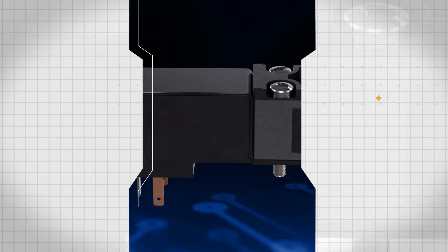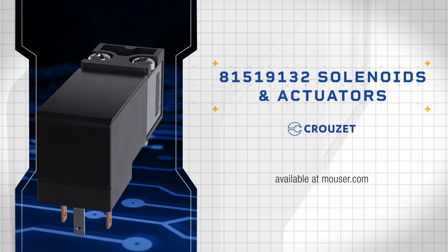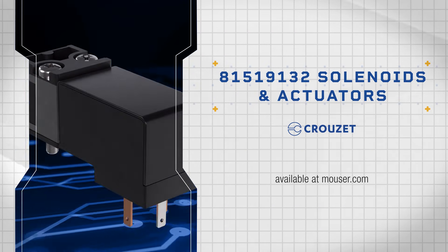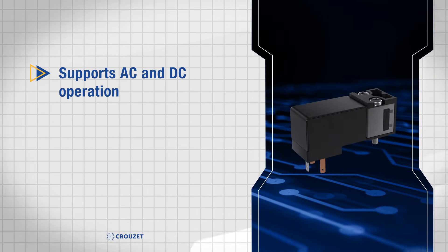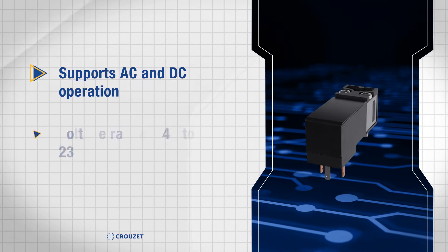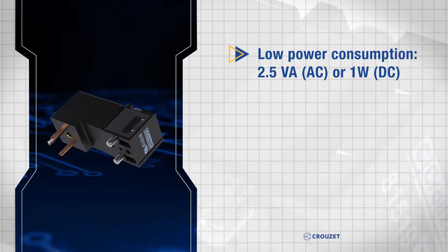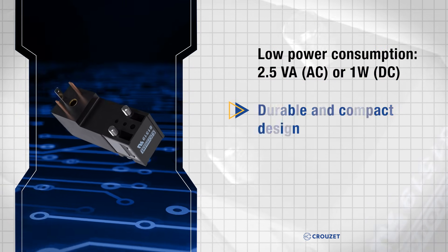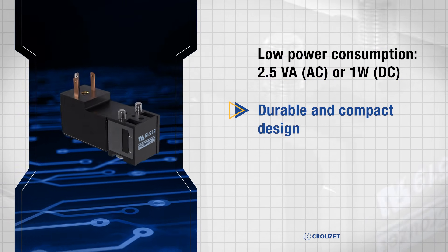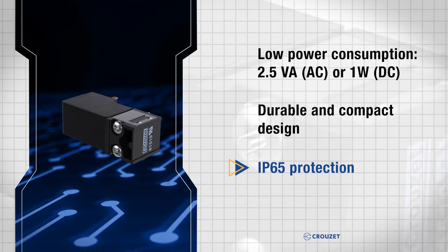Crouzet 8151-9132 solenoids and actuators provide reliable, efficient solutions for diverse industrial applications. These miniature solenoid valves support both AC and DC operation with voltages ranging from 24 volts to 230 volts. With a low power consumption of 2.5 volt-amperes AC or 1 watt DC, these valves feature a durable and compact design with IP65 protection, ensuring reliability in harsh environments.